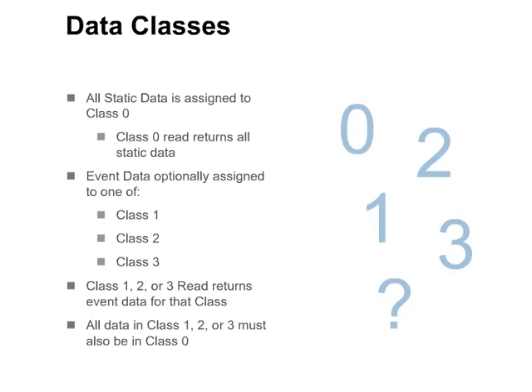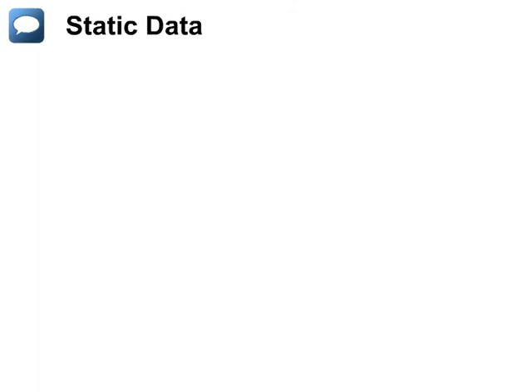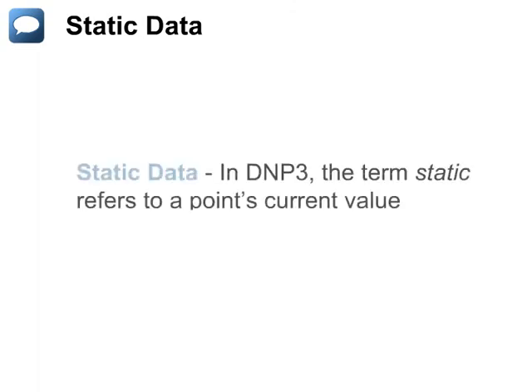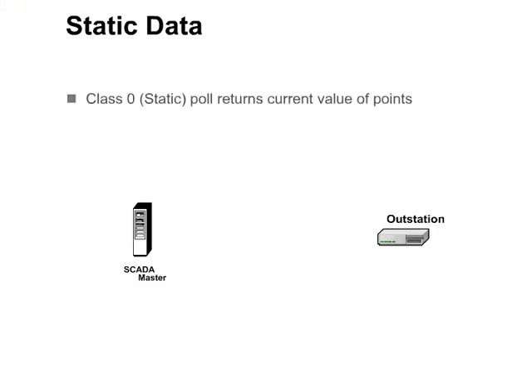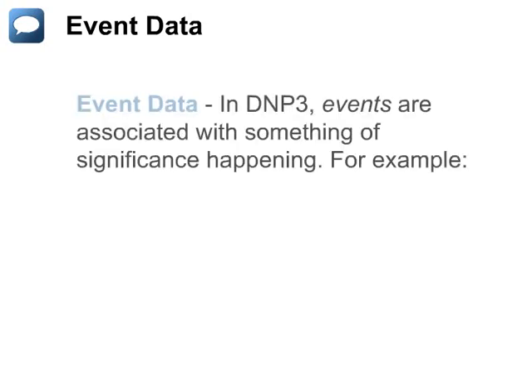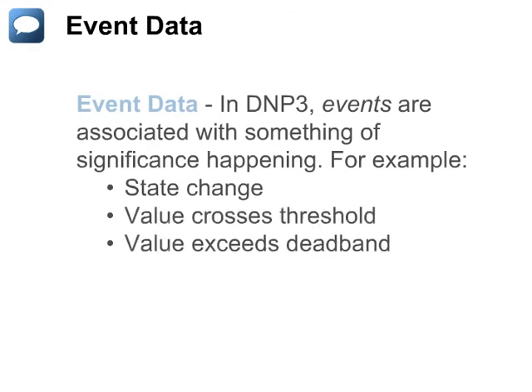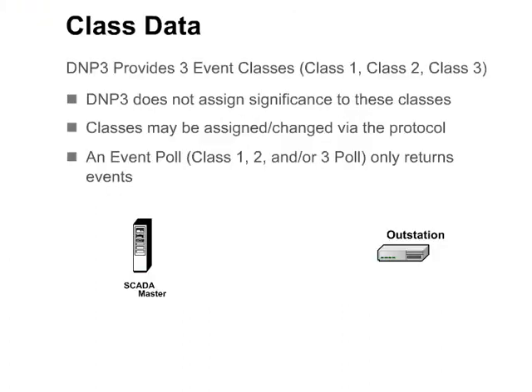In DNP, the term static data refers to a point's current value. A class 0 poll returns the current value for all points in class 0. Any points in class 1, 2, or 3 must also be in class 0. Events are associated with something of significance happening — most commonly a state change or a change in the data's value. However, it could also be because a value crossed a threshold or exceeds a deadband, or it might represent a snapshot taken at a particular time. DNP supports three event classes, called class 1, class 2, and class 3.